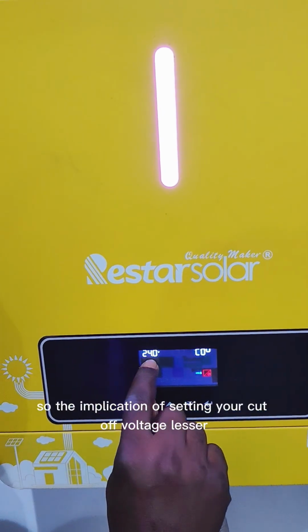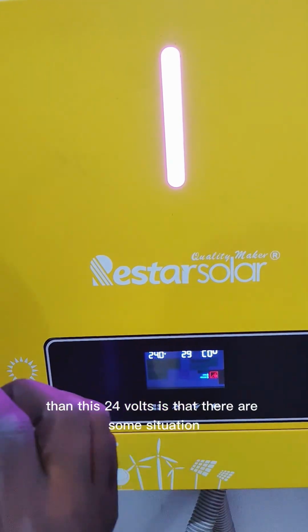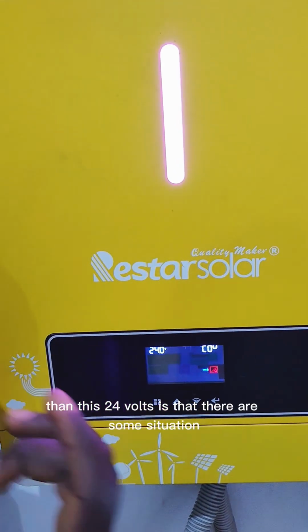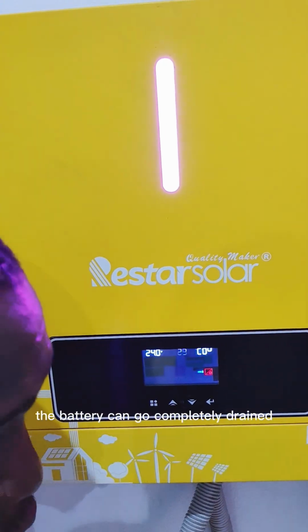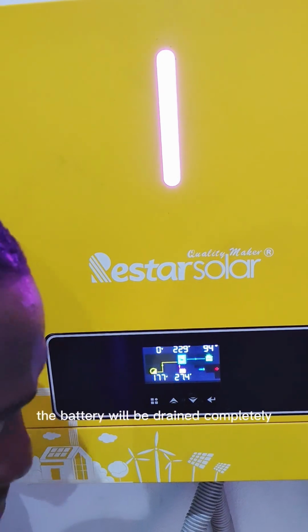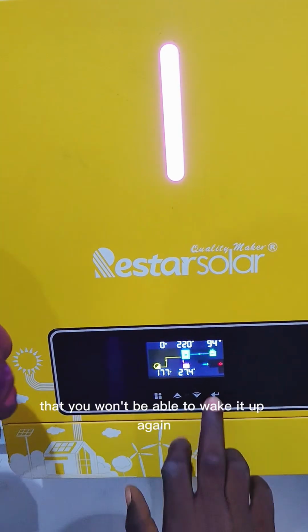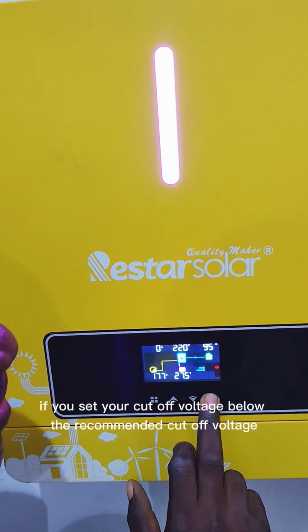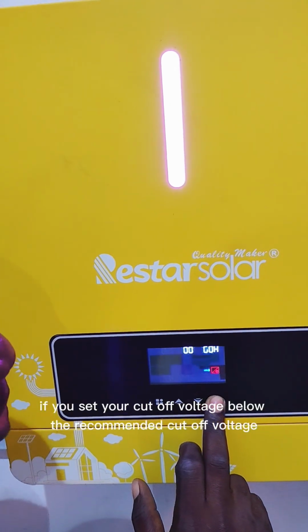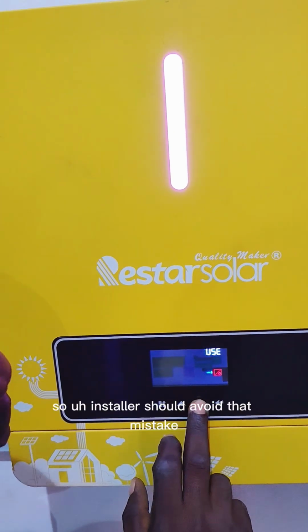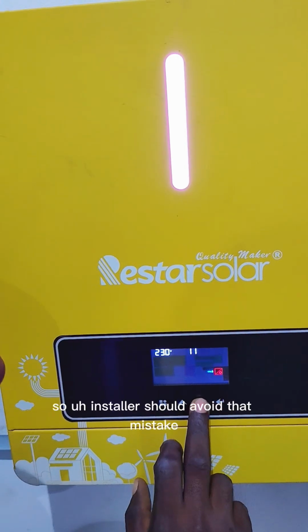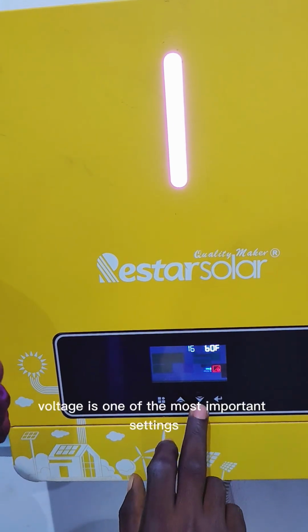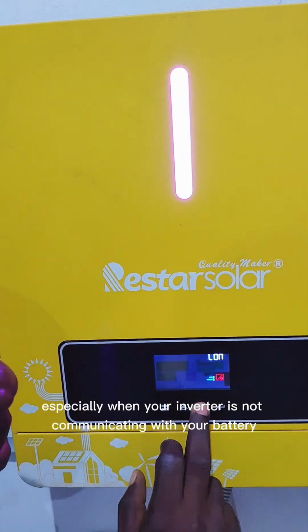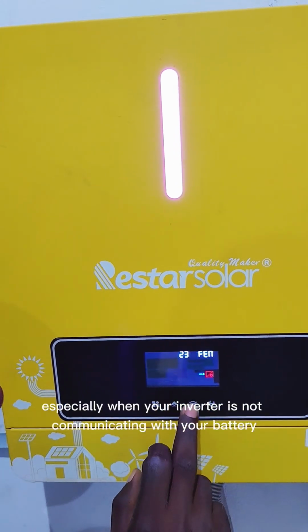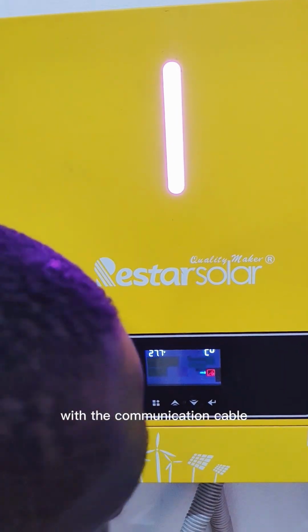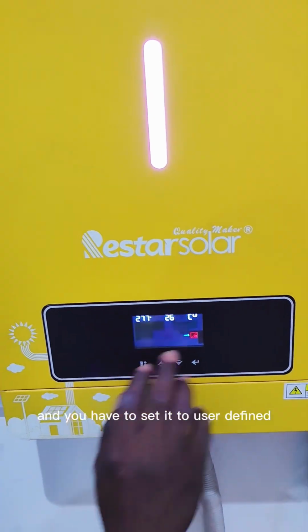So the implication of setting your cutoff voltage lower than this 24 volts is that there are some situations whereby the battery can go completely drained. The battery will be drained completely, so that you won't be able to wake it up again. That is if you set your cutoff voltage below the recommended cutoff voltage. So installers should avoid that mistake. Pay attention to your cutoff voltage. It is one of the most important settings, especially when your inverter is not communicating with your battery with the communication cable, and you have to set it to user defined.